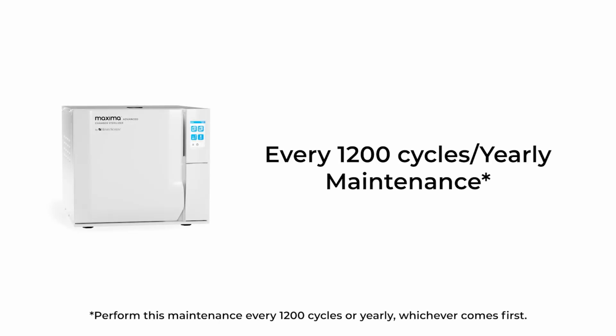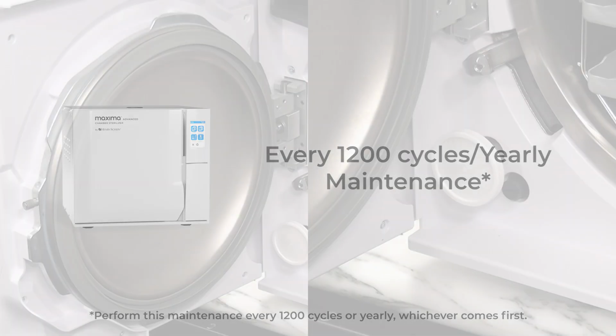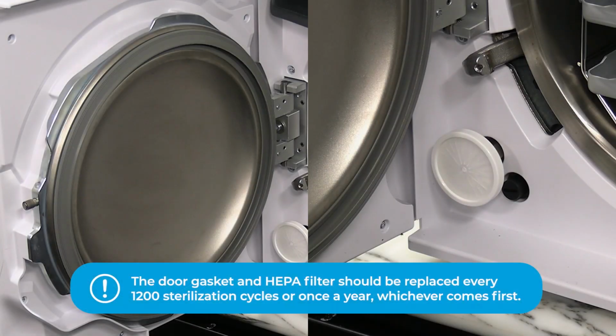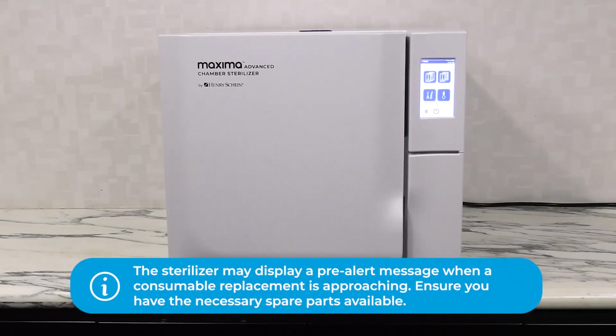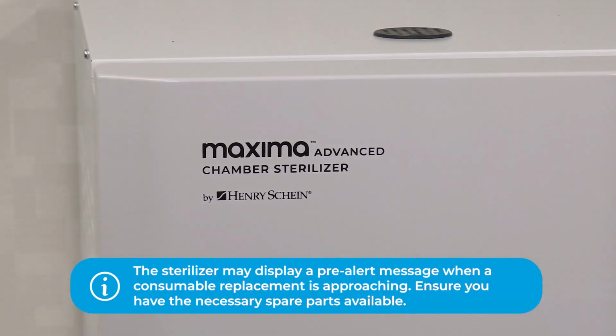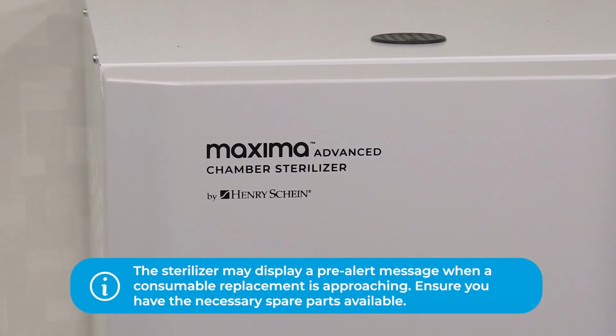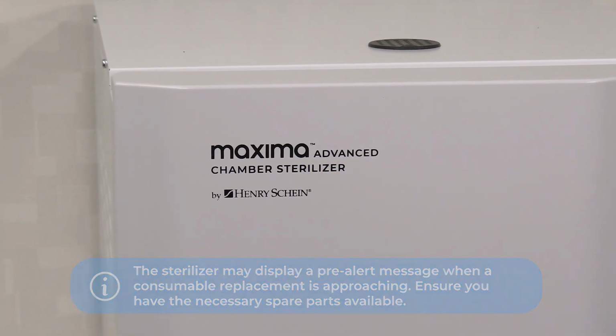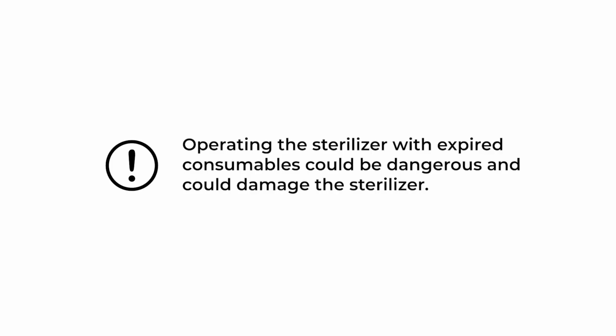Yearly or 1200 cycles maintenance. The door gasket and HEPA filter should be replaced every 1200 sterilization cycles, or once a year, whichever comes first. The sterilizer may display a pre-alert message when a consumable replacement is approaching. Ensure you have the necessary spare parts available. Operating the sterilizer with expired consumables could be dangerous and could damage the sterilizer.